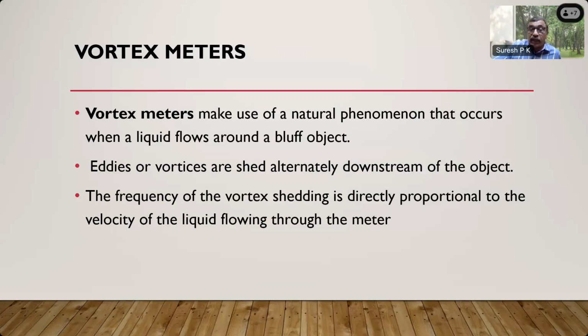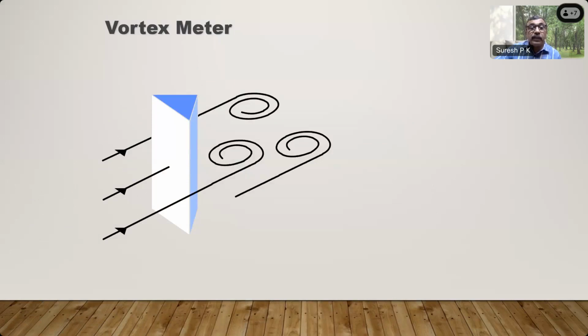That is, a bluff body is placed in a flow, like a flag fluttering. You would have seen flags fluttering. Flags flutter because the flag post works as a bluff body, and the downstream vortices make the flag flutter this way or that way due to the vortex pressure drop. The frequency of the vortices generated, or the fluttering, will be proportional to the velocity. If the velocity of the air is high, the vortices are formed at a more frequent rate than at low velocity. The frequency of vortex shedding is directly proportional to the velocity of the liquid flowing through the meter. This is what a vortex meter is. There is a bluff body, and you see that vortices are being shed downstream of the body.